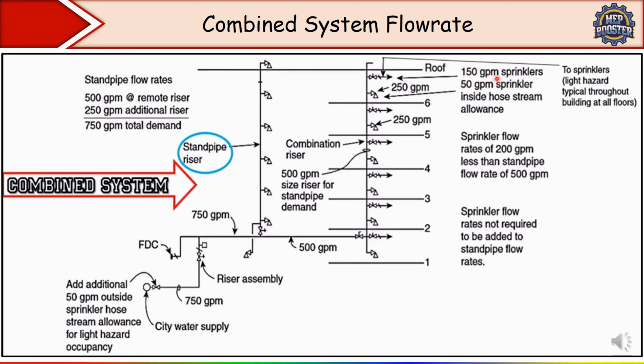If you see, the sprinkler flow rate is given, as I discussed earlier, that in case of light hazard, 150 GPM sprinkler is given, okay, plus 50 GPM inside hose stream allowance, an additional requirement per floor. So the total sprinkler flow rate is 200 GPM, which is not required to be added to the standpipe flow rate. This means that the flow demand for sprinkler does not need to be summed with the standpipe demand. In this case, normally the sprinkler flow rate is less than the standpipe flow rate. So we always have to consider the larger flow rate, which is 500, plus this additional, so in total we have got 750 GPM. Clear? In this way we need to calculate the flow rate for the combined system; whichever is greater, you have to consider.